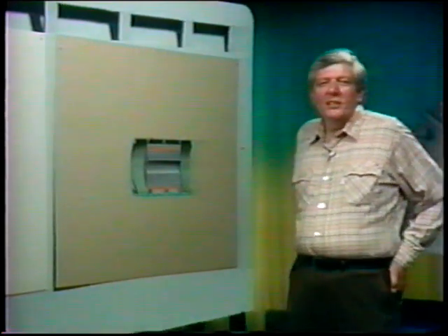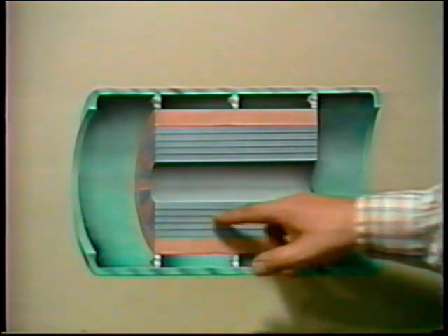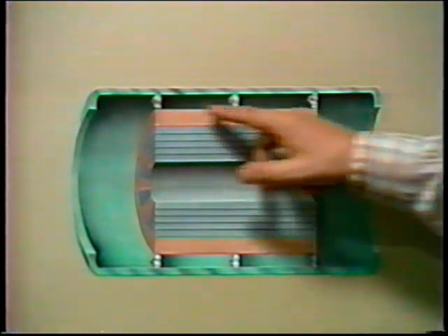Let's go on now and cover the other major generator part, the stator. Stators can be built a number of different ways, but they all have certain common features. Stator windings, a stator core, which concentrates and directs the magnetic field within the stator. A stator frame, which contains and supports the core and windings. And end bells, which close the end of the generator's frame.